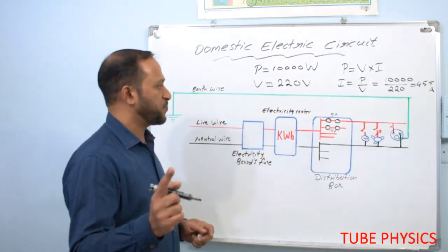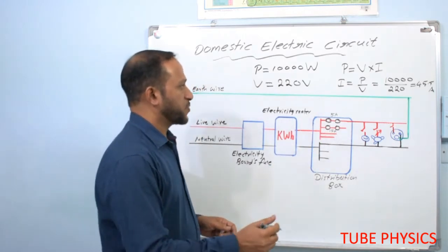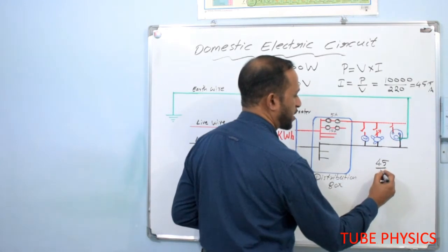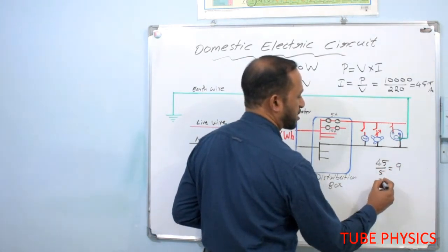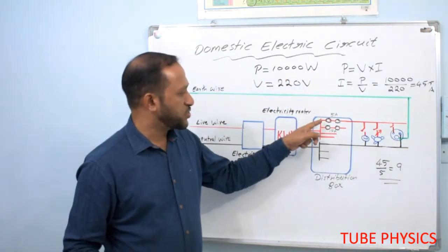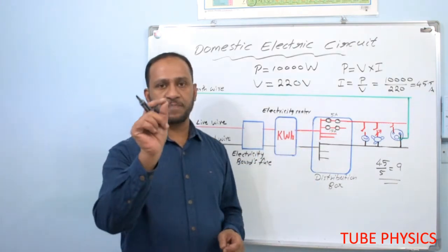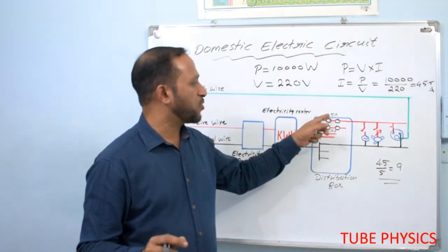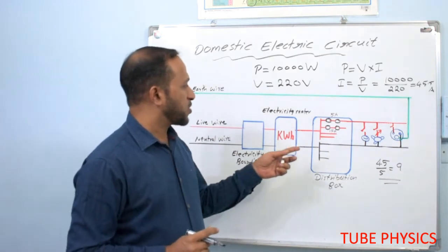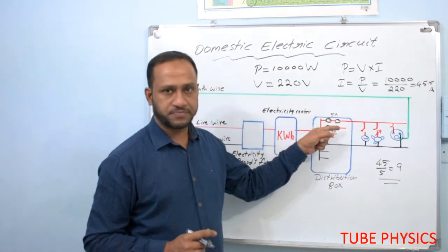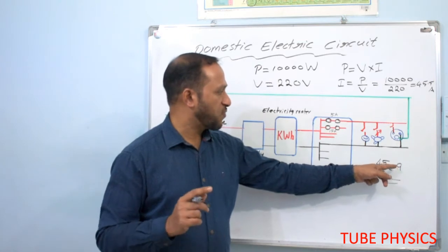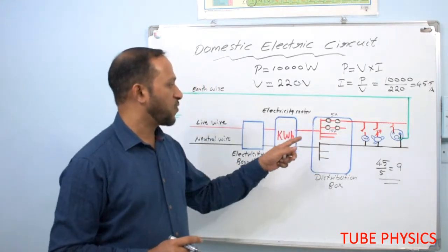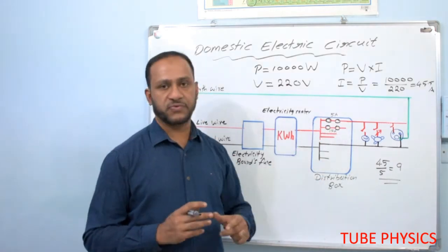The main wire up to the distribution box should be a special wire able to carry 45 ampere of current. Now we can calculate how many branches are needed. We know that in normal wiring the maximum current is 5 ampere per line. Here we have 45 ampere total, so 45 divided by 5 equals 9 branches required. In the distribution box, divide the live wire into 9 branches, each with a fuse wire or circuit breaker that will burn or trip if current exceeds 5 ampere. You can also connect one 15 ampere line for high power devices, making 6 branches of 5 ampere and one branch of 15 ampere.